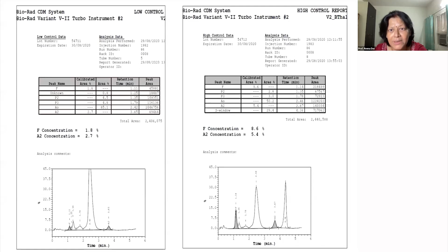If your calibrator has gone through well, and your controls are working properly, the normal and the high control, now you have to run your test samples. So this is another view of the hemoglobin HPLC. Now, what are the advantages of a hemoglobin HPLC system? It's a fully automated system. There's good speed and accuracy. You have to use calibrators and controls.